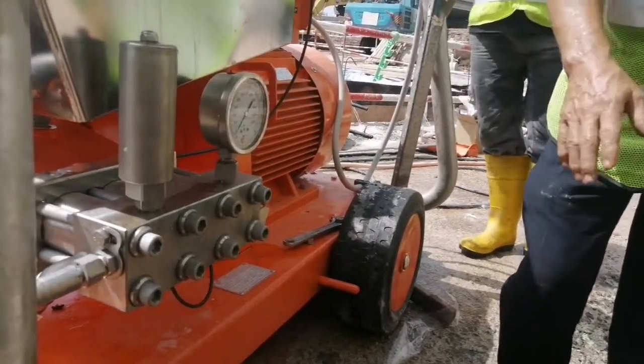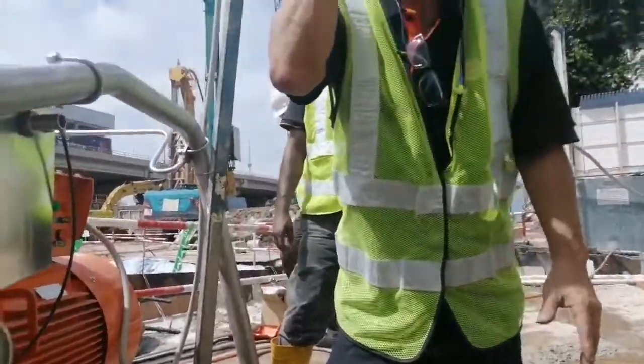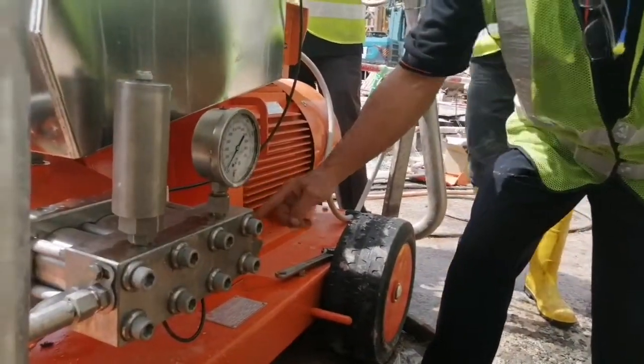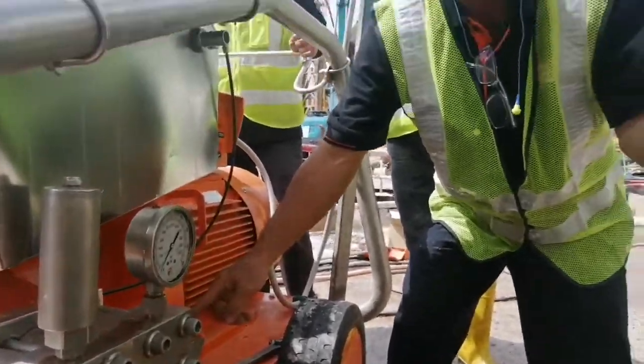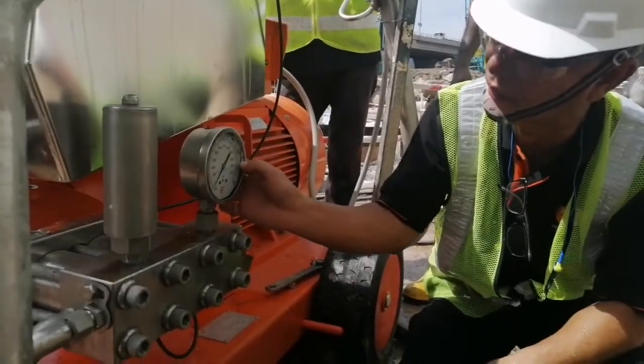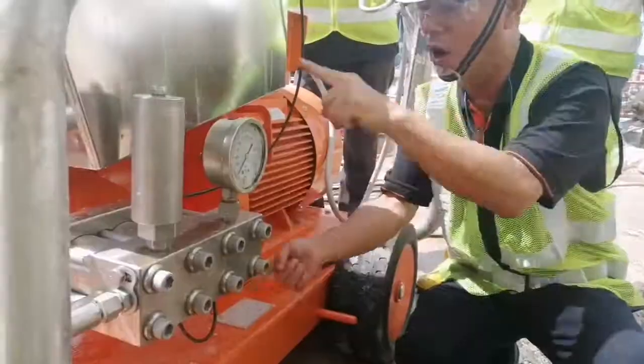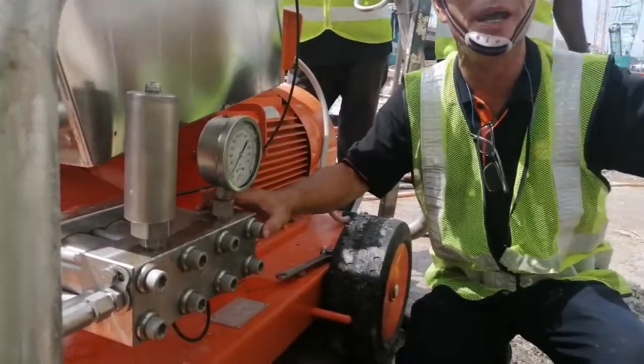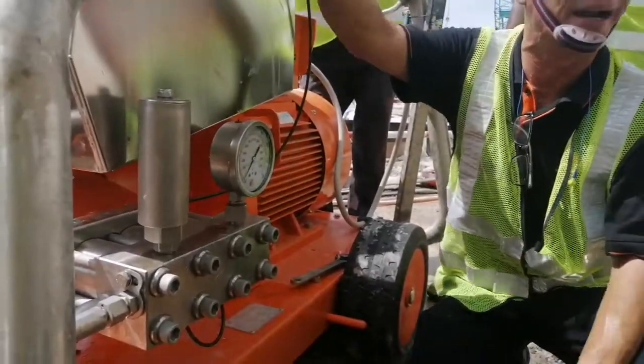Shake — maybe nozzle block. Okay, if you don't know, hold. This one here: rupture disc. Inside here got one disc. If the pressure goes 21,000, this one pump — water all comes out here. This one will be a major block, that means the nozzle completely block, the pressure goes very high.